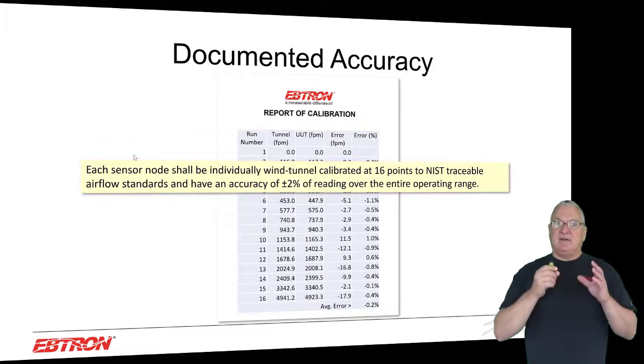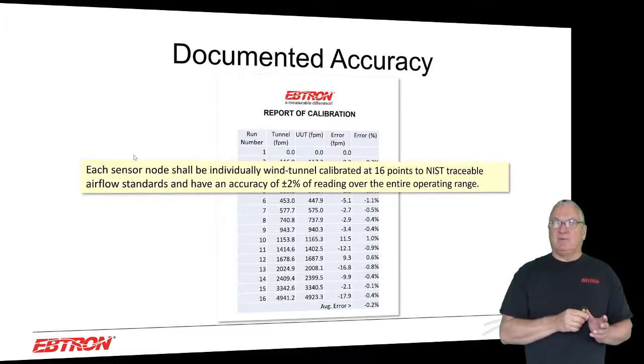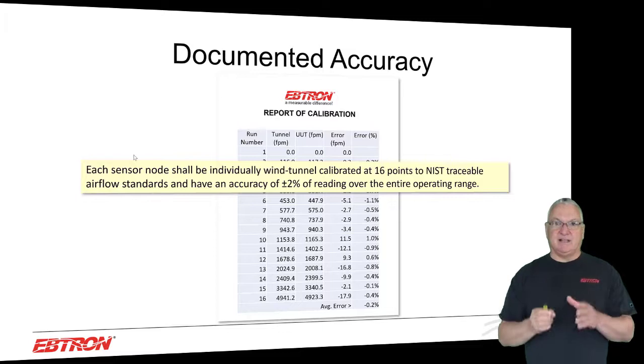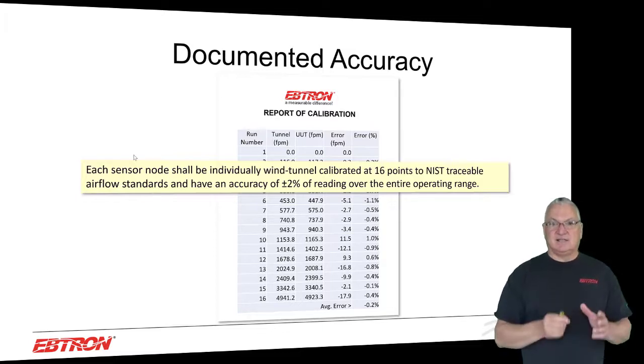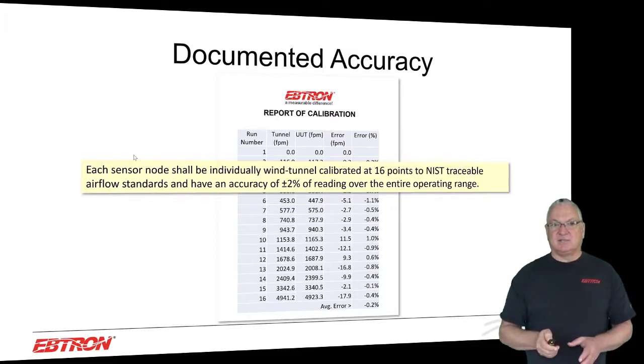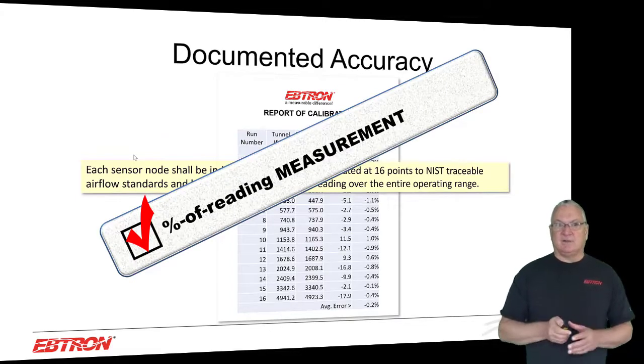Okay, that doesn't mean that we've tested one unit at 20 points or 25 points. It means that we calibrate each sensor at 16 points to these NIST traceable standards, and we have documented accuracy. So that's how we come up with our percent of reading measurement claim.